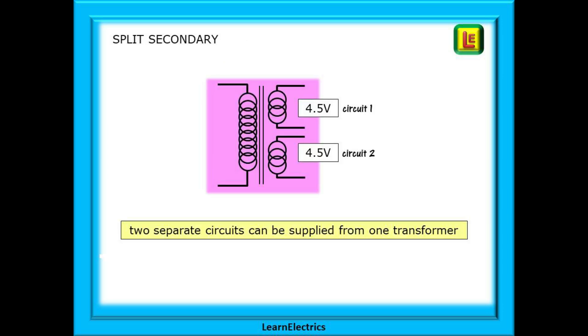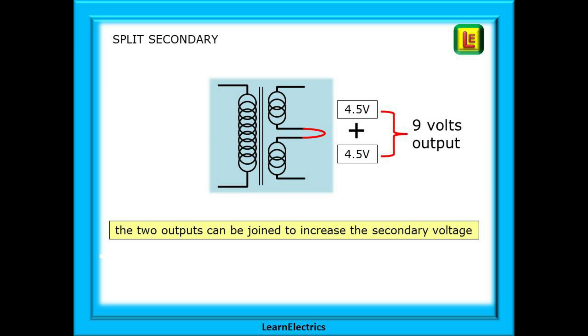Some transformers have split windings and you may come across these in your work. In this drawing we have two secondary windings each giving four and a half volts. This means that two separate circuits can be supplied from the same transformer or we can join the two secondary windings as shown and have a 9 volt output.